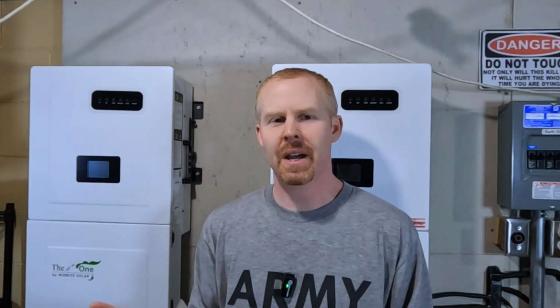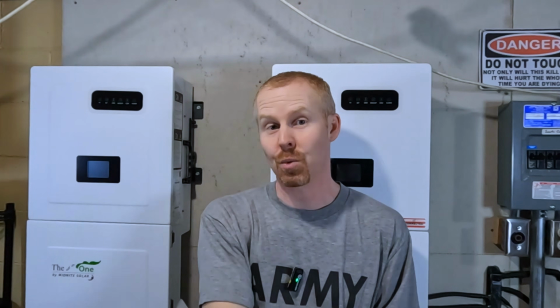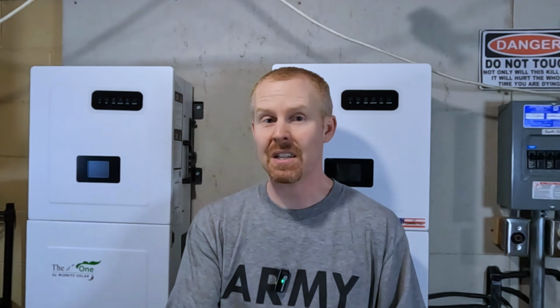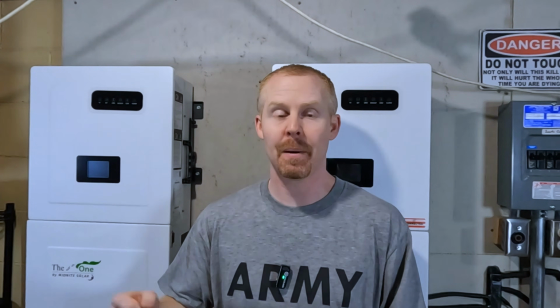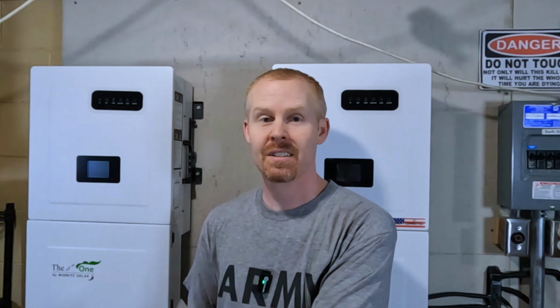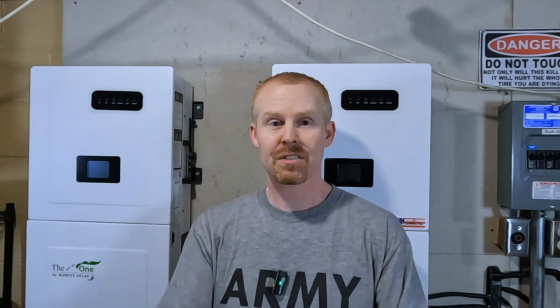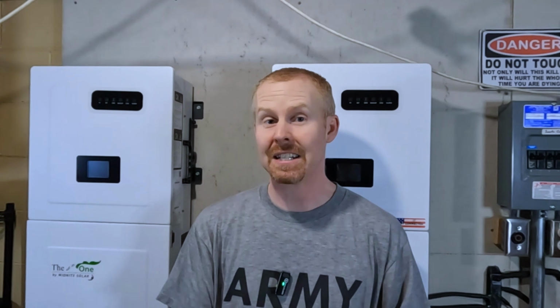So I went through all the specs in a previous video, which I'll link to here. But if we put both of these together, that gives us the ability for, like I said, 20 kilowatts of output straight from the batteries, almost 23 kilowatts when you include PV. Each inverter can handle up to 15 kilowatts of PV on its own. So that gives you a combined total PV input of 30 kilowatts across 6 MPPT trackers. Plus, you could handle up to 10 kilowatts of AC coupled PV per inverter, giving you an additional total of 20 kilowatts of PV input.